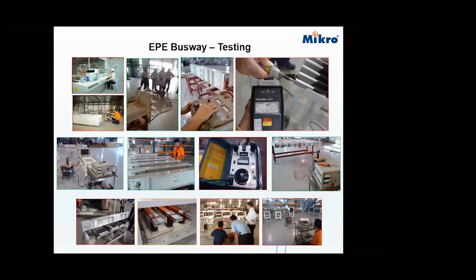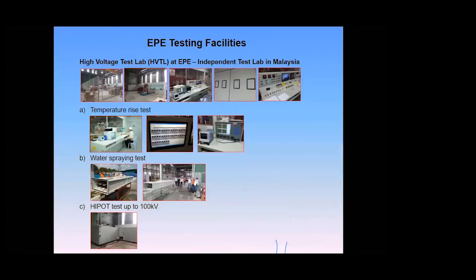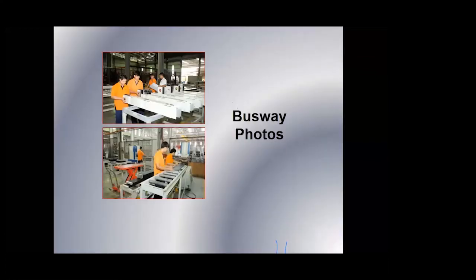Here are some photos to show the testing in action — megger tests, also with our customers present. We also have an independent test lab at the EPE factory — a third-party test called HVTL — where you can always request a temperature rise test upon special request, as well as hipot testing up to 100 kV.